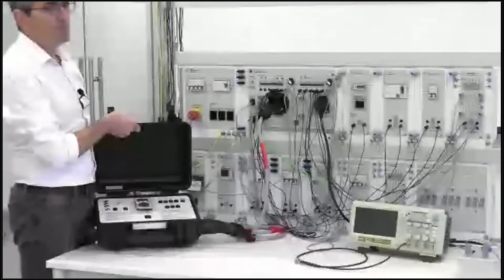If I change my cable ampacity here to 20 amp, you see that now I get a fault, because it tells me that the cable connected here doesn't have the capacity required to accept the charging current this station is providing. So the station will refuse charging the car because it sees the cable doesn't have the proper capacity. Of course, in this case, I am simulating a cable of different ampacity with these switches.